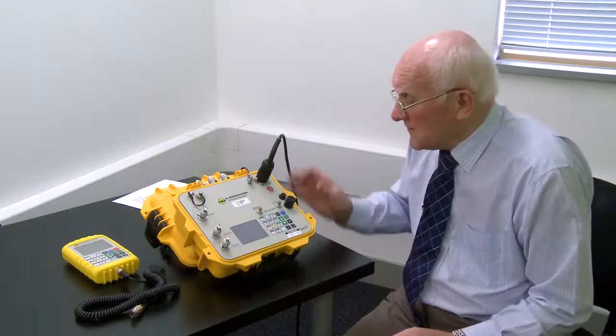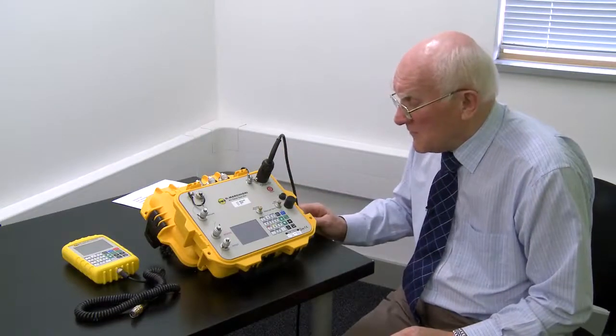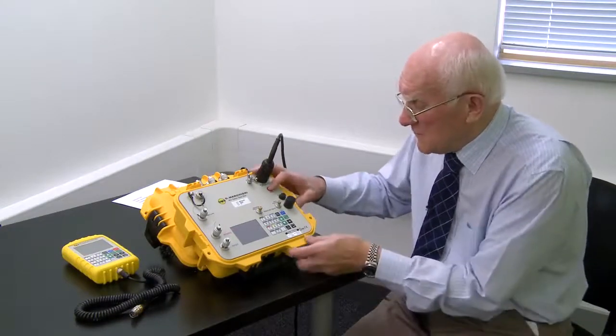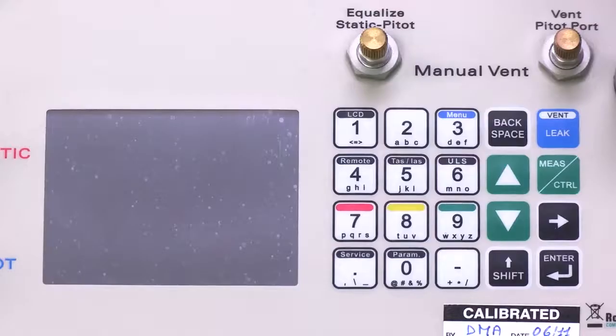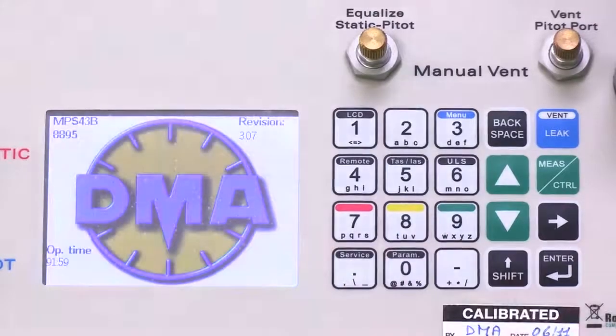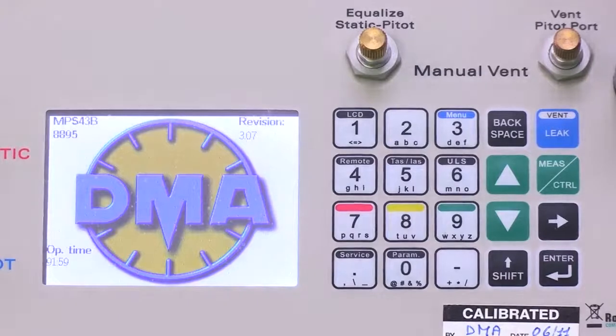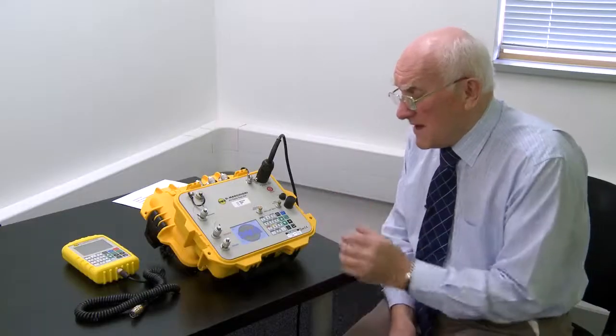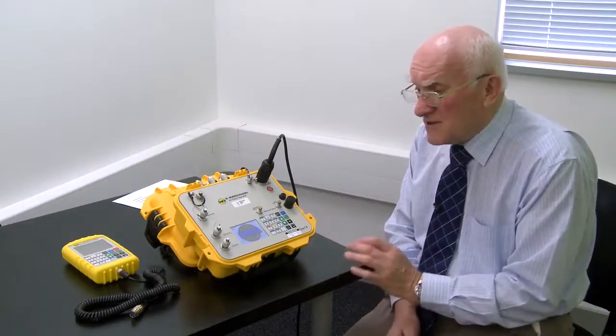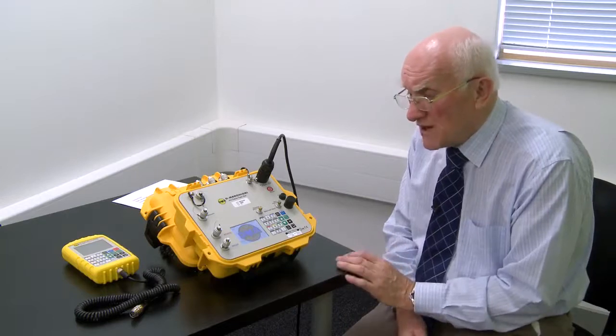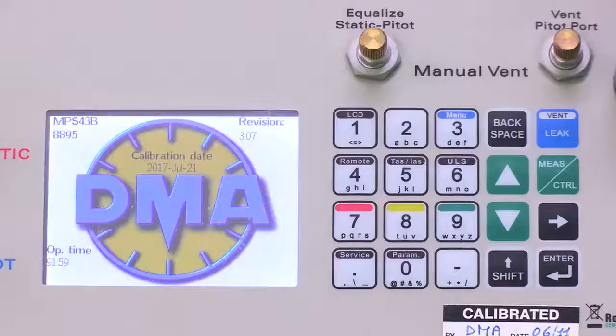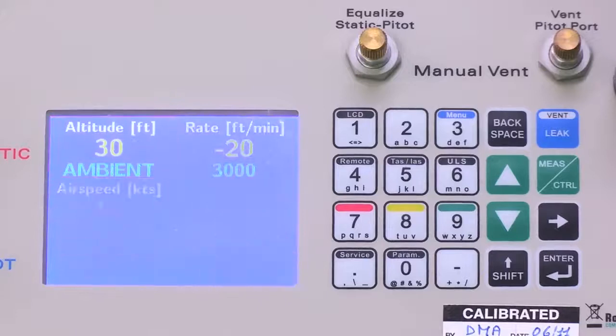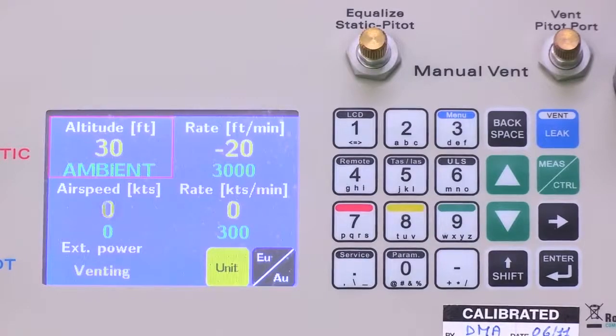Okay, now we've connected the AC supply, we can do a startup. We press the power key and the instrument goes through its own startup routine, giving serial numbers, running hours, and when it was last calibrated. From there, it follows a standard procedure, always venting to ground level, so that when you start using the instrument, it automatically goes to ambient.